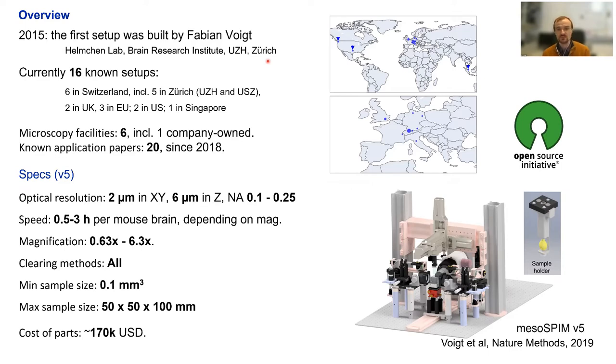The latest published version, mesoSPIM version 5, has these specs: optical resolution of about 2 microns in lateral dimensions XY, 6 microns in Z, and NA depends on magnification from 0.1 to 0.25. It is fast as you could see in the demo. Mouse brain depending on magnification takes from 30 minutes to a few hours. It is compatible with all clearing methods and a big range of sample sizes. The current cost is about 170k in parts, and most of this is the laser.